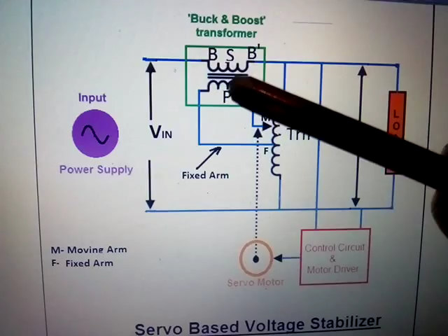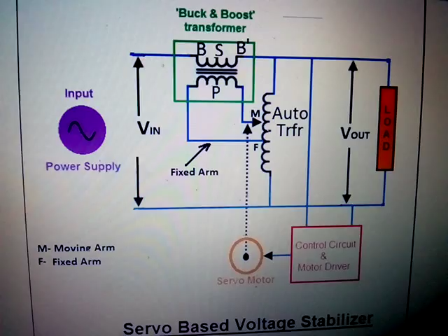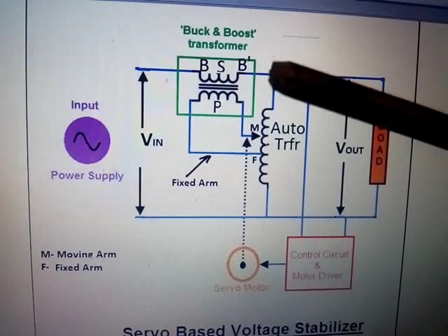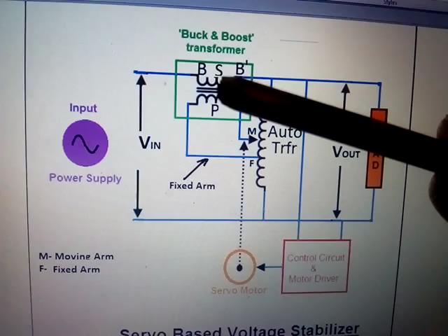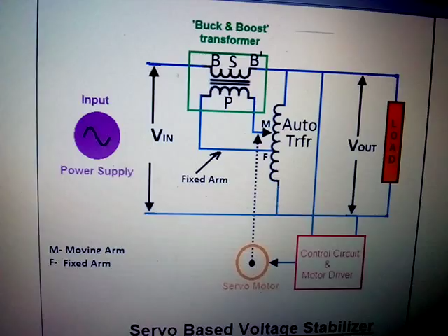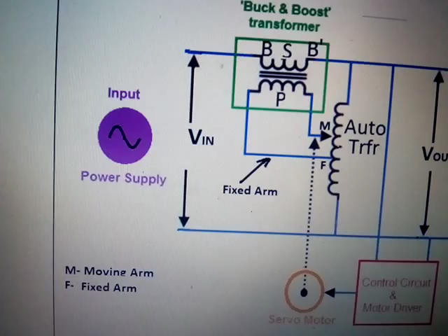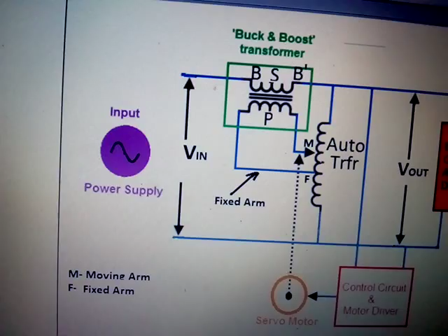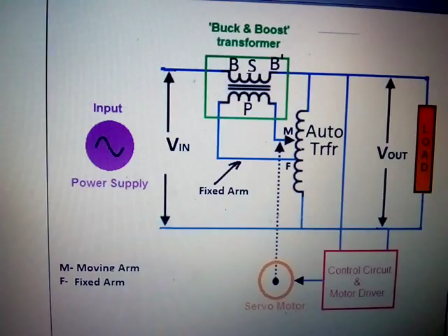One terminal of the primary of the buck boost transformer is connected at the middle of the auto transformer. If the moving terminal is above the fixed middle terminal, the input voltage supplied to the buck boost transformer will be in one phase. If it is below the fixed terminal, the phase applied to the primary of the buck boost transformer will be reversed.